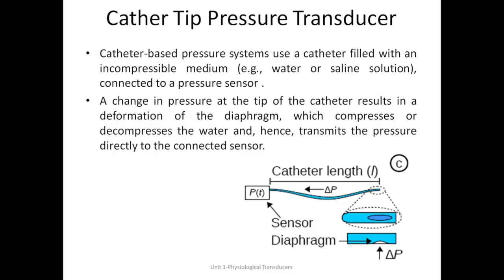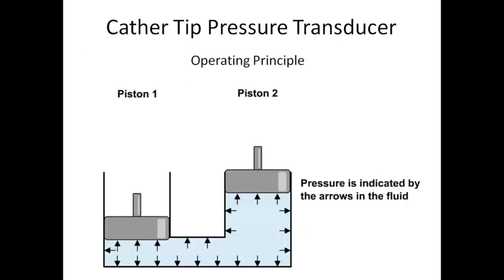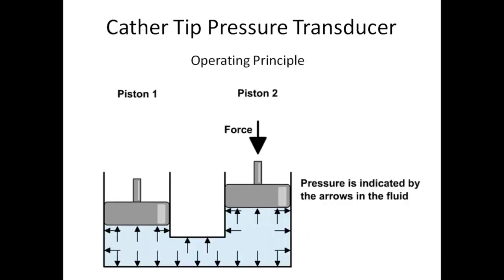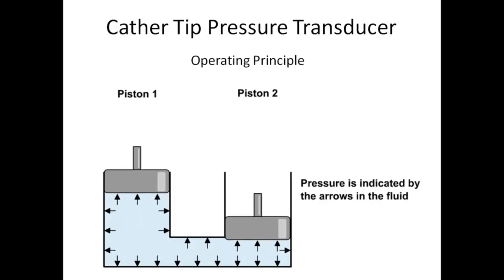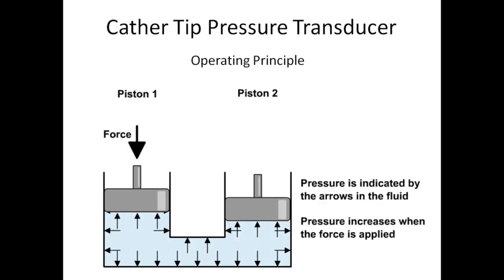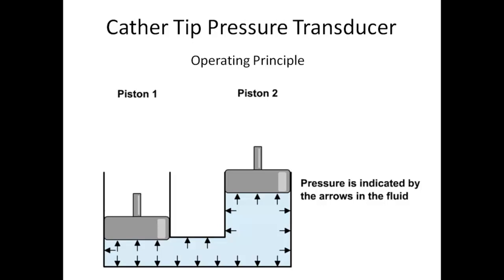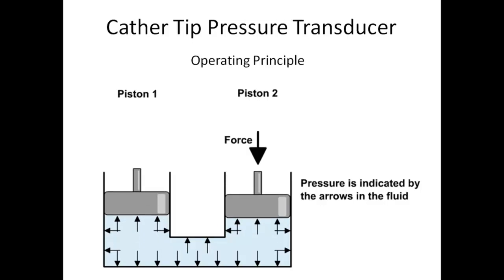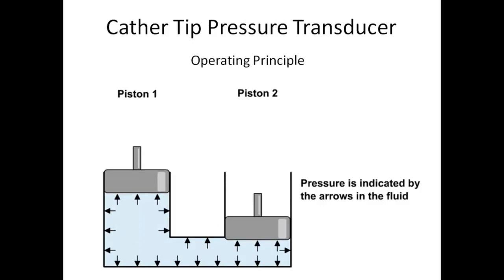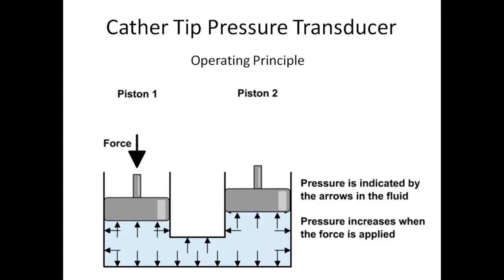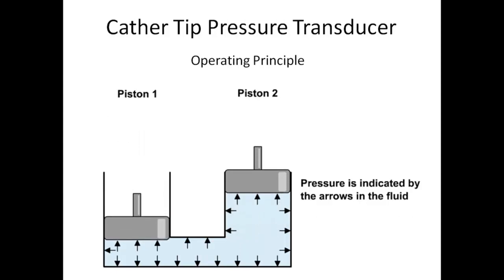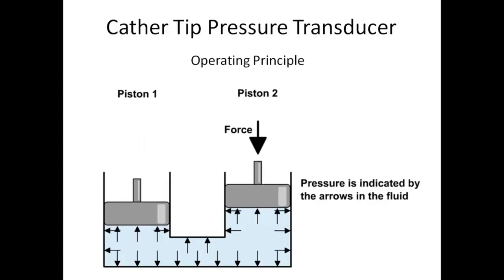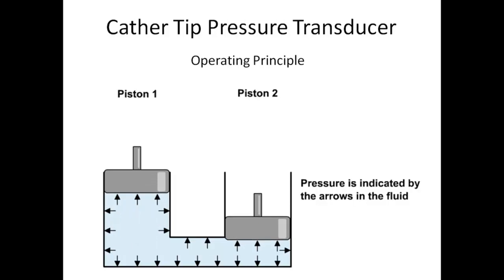Okay, so like this, we can use a catheter based pressure transducer for a very accurate measurement from within the body. Okay, so you can see this is what it is based upon. The operating principle is something like this. If you press from one side, and this closed cavity is filled with an incompressible liquid, the other side will bulge out. The same thing is happening with the help of catheters.